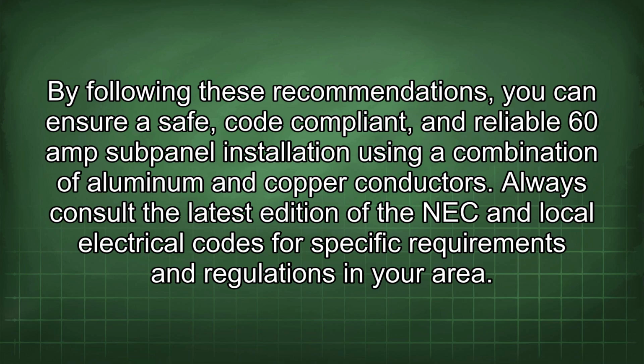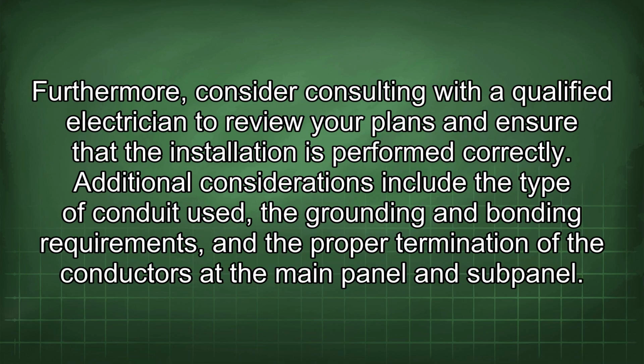By following these recommendations, you can ensure a safe, code-compliant, and reliable 60 amp subpanel installation using a combination of aluminum and copper conductors. Always consult the latest edition of the NEC and local electrical codes for specific requirements and regulations in your area. Furthermore, consider consulting with a qualified electrician to review your plans and ensure that the installation is performed correctly. Additional considerations include the type of conduit used, the grounding and bonding requirements, and the proper termination of the conductors at the main panel and subpanel.